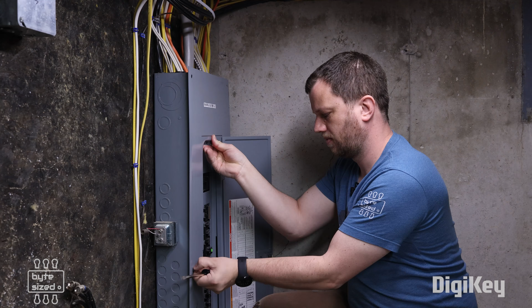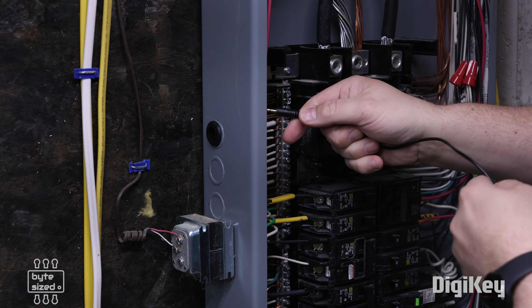One important thing to note is to use a current transformer that will fit comfortably around the wire you're trying to measure - you don't want one that won't close all the way around. Also, you should never close the current transformer without the burden resistor in place, which means I won't be closing these current transformers until I have them plugged into the PCB.